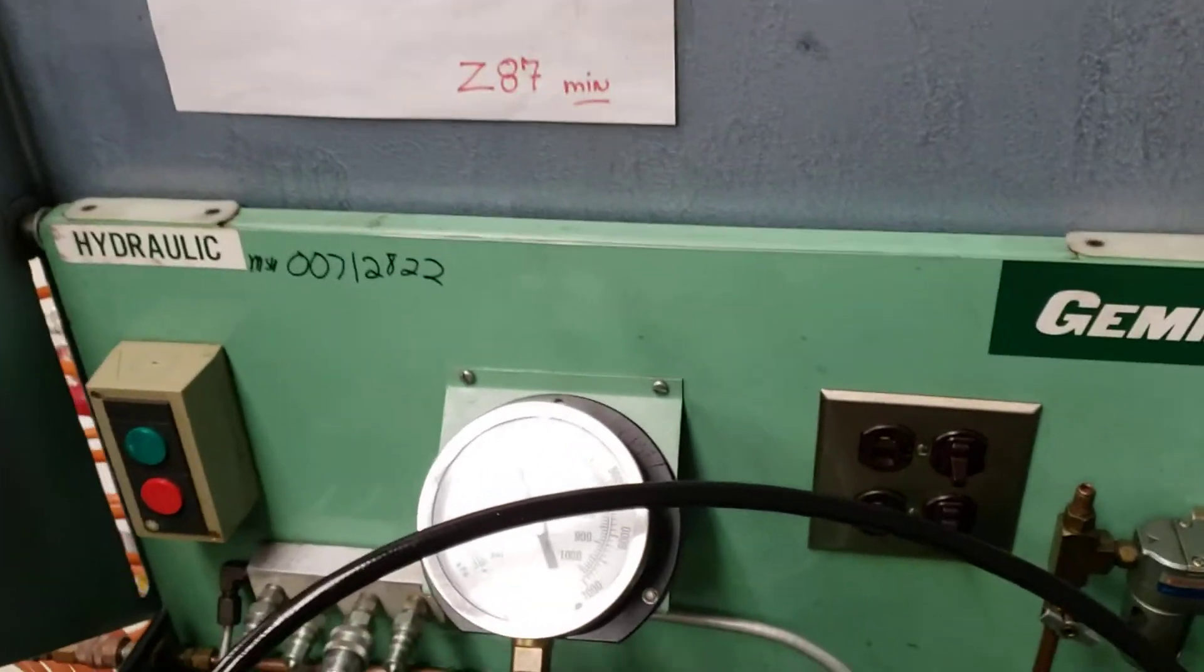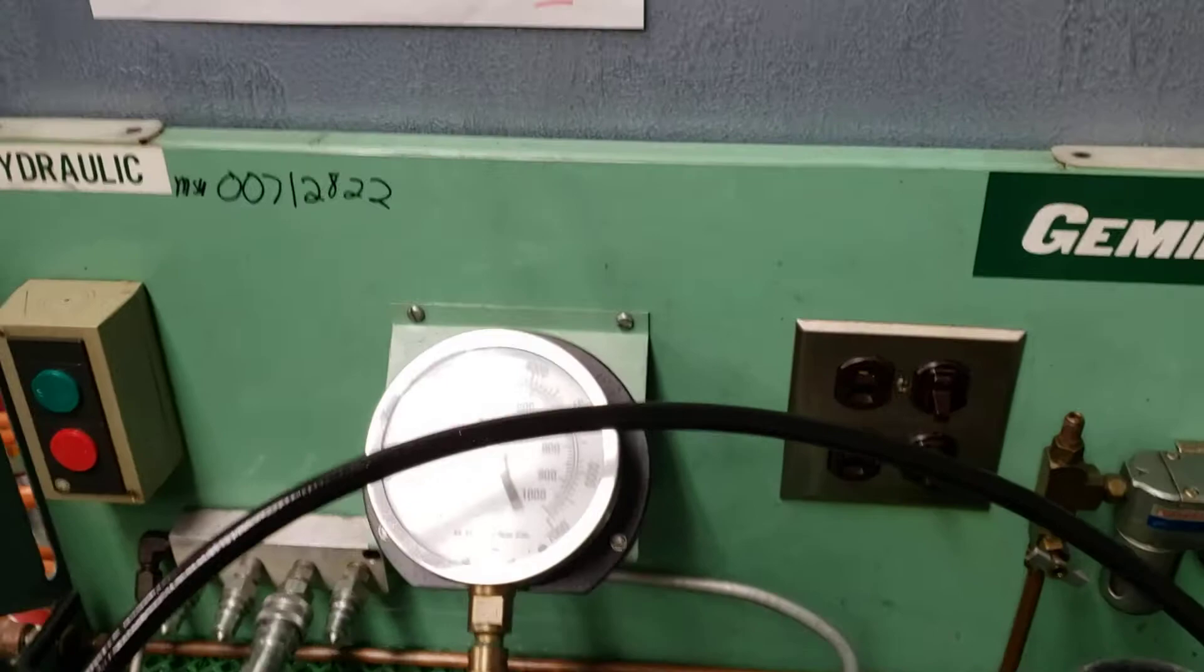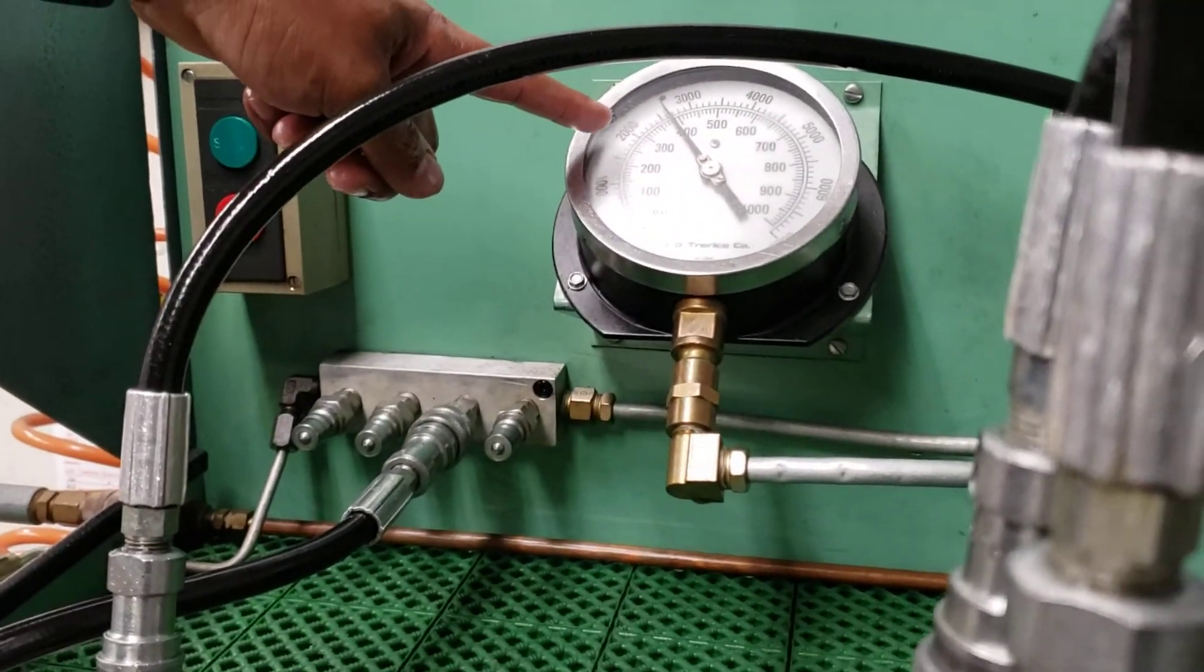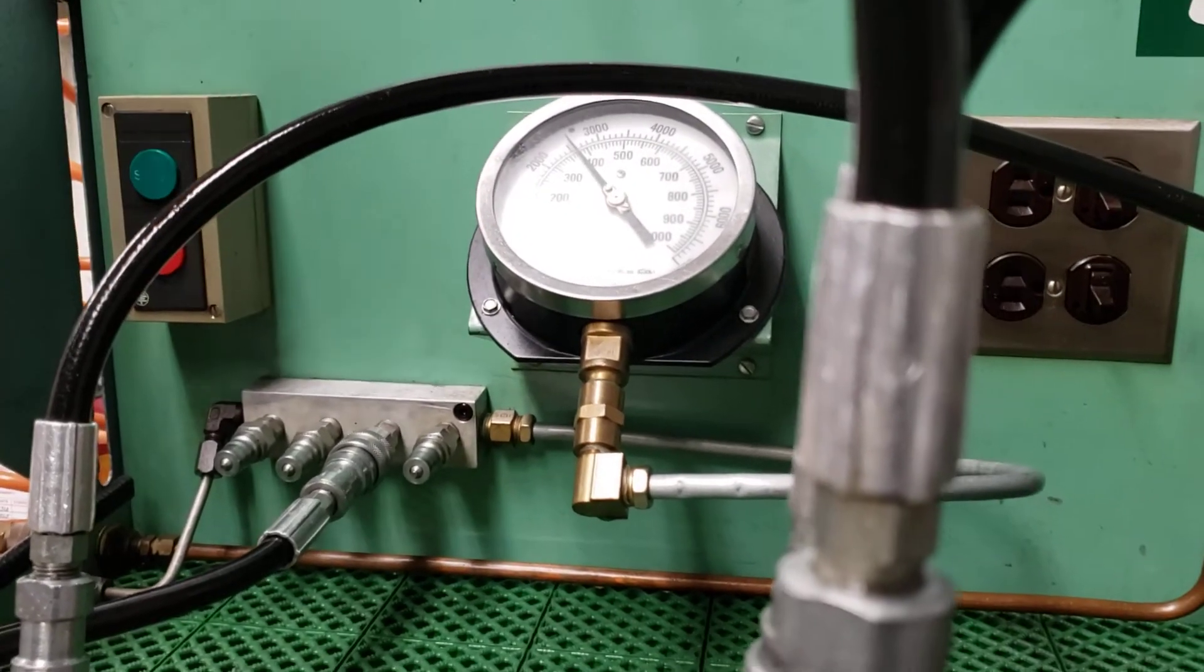It's going down. Basically if there is no flow, the system is still pressurized but you can tell there may be a little bit of leak somewhere. That's why it's going down, it's not able to hold the pressure.